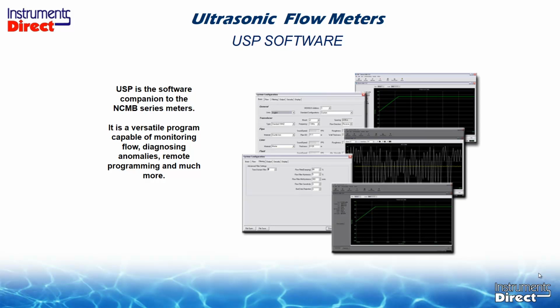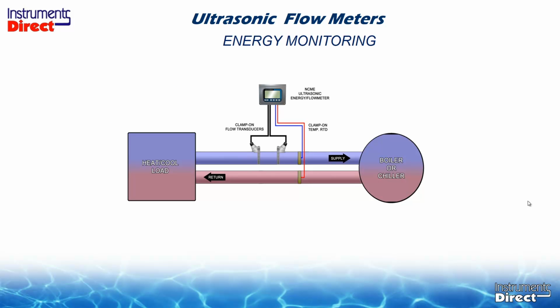Now, if you want to get fancy, you can also use a laptop or a computer to do a basic setup. You can also check out the upper level of diagnostics or set it up for an energy or BTU application, providing you have the energy option. This is accomplished by combining flow and temperature. The flow transducer is typically on the supply line, and they strap on the RTDs, one on the supply line and one on the return line. The goal is to monitor the temperature differential between the supply and the return line with a non-invasive temperature sensor.